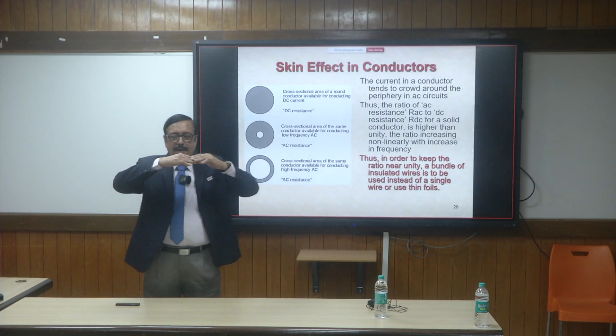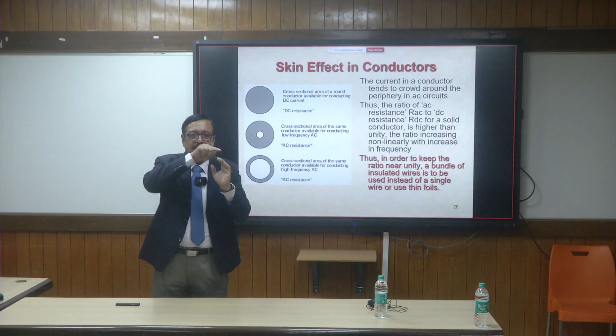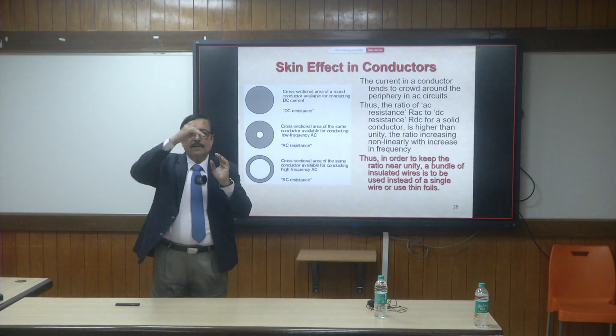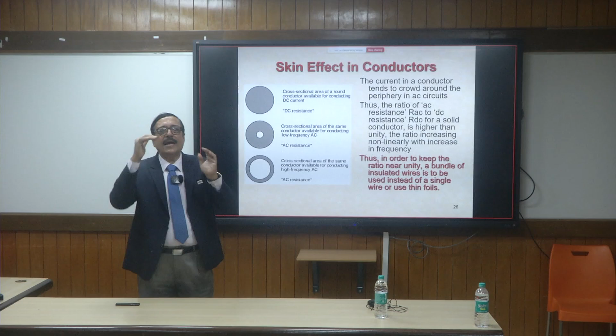The problem in making foil is you can't expect to put parallel foils for large current applications, because they will never share equally. When you have parallel conductors, either in a bent condition, the outer one has a longer path length than the inner. Because its radius is larger, most of the current will try to flow through the inner, and the outer exists there but will not carry much of the current. So you lose. So what we do in bigger transformers is we transpose the wires. So you change the position of the wires, make the outer for some time come to the inner, and so on.